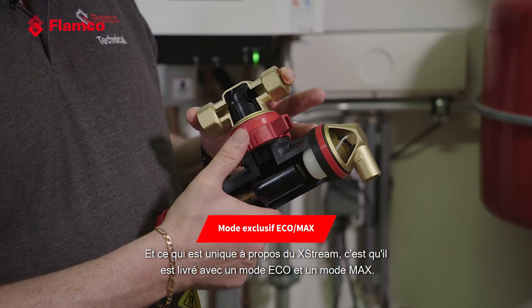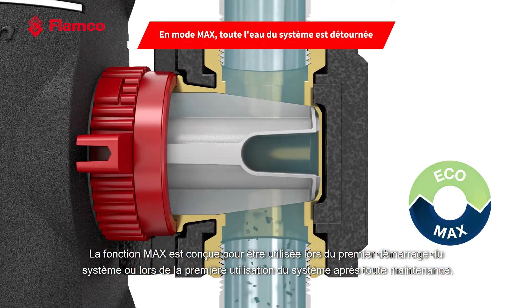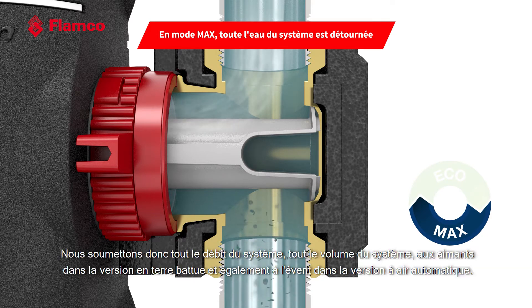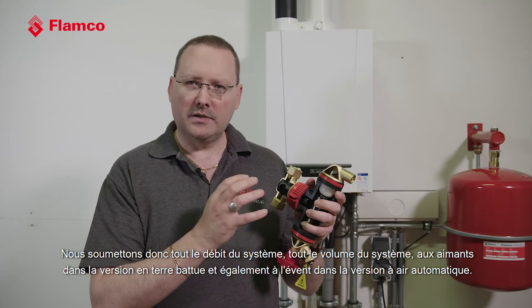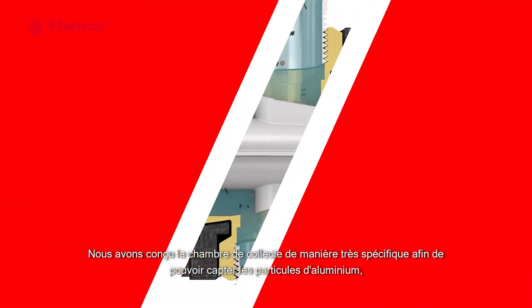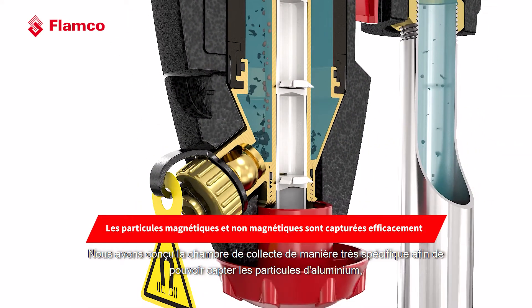What's unique about the XStream is that they all come with an Eco and Max function. The Max function is designed to be used when you're first starting up the system or running it after any maintenance. With the Max function, all of the fluid is diverted through the separator, so we're subjecting the entire system flow and the entire system volume to the magnets in the dirt version and also to the air vent in the automatic air version.